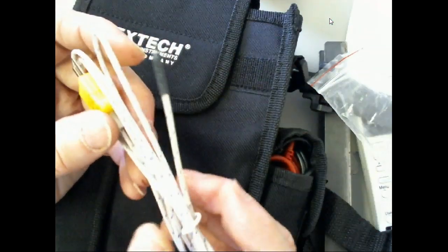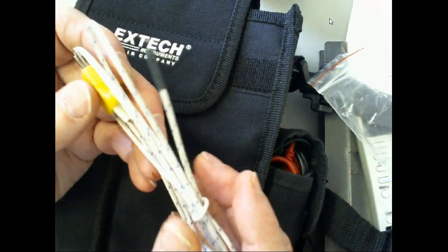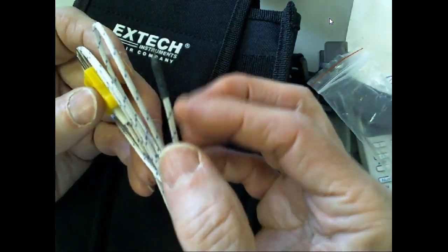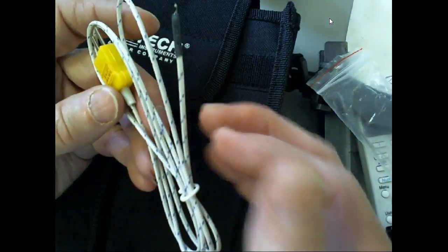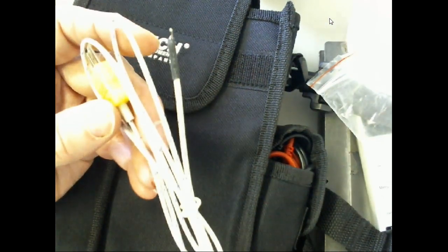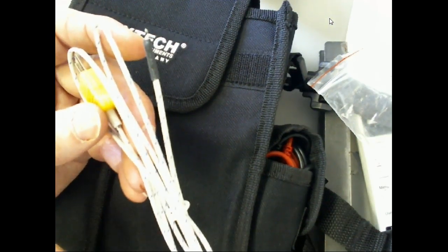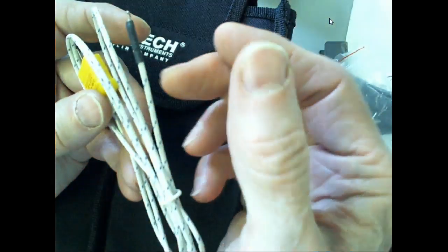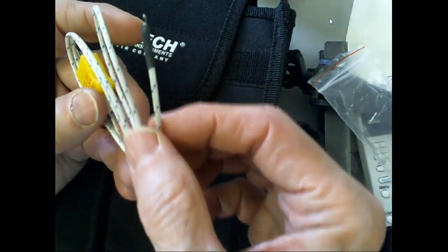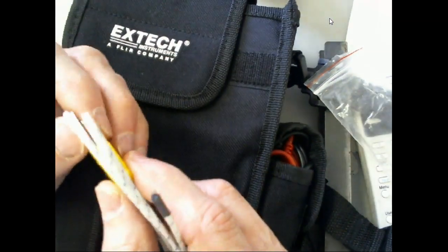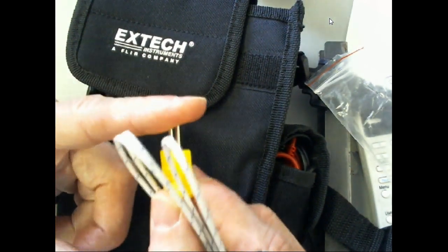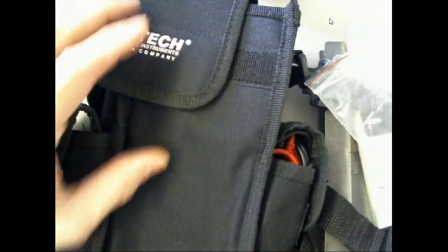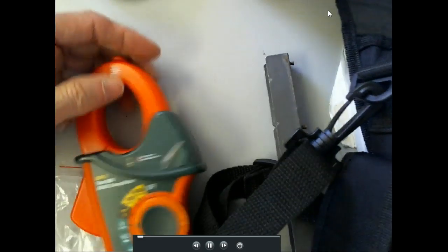Now, there's something very strange about this, is that if I was to come up here and take these metals and bond it with copper, then I've just created another thermocouple. So what you have to do is maintain the two metals all the way back to the indicator, whatever is sensing the temperature. So this guy right here has got a temperature gauge on it.